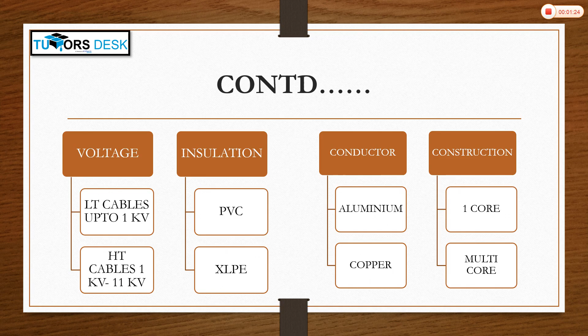Now, the major concern for electrical engineers is proper selection of cables. First of all, we should know why proper sizing of electrical cables is required. Electrical cables should be sized properly so that they can operate continuously under full load conditions without damage to their insulation; second, withstand the short circuit conditions flowing through cables; and third, avoid excessive voltage drops.